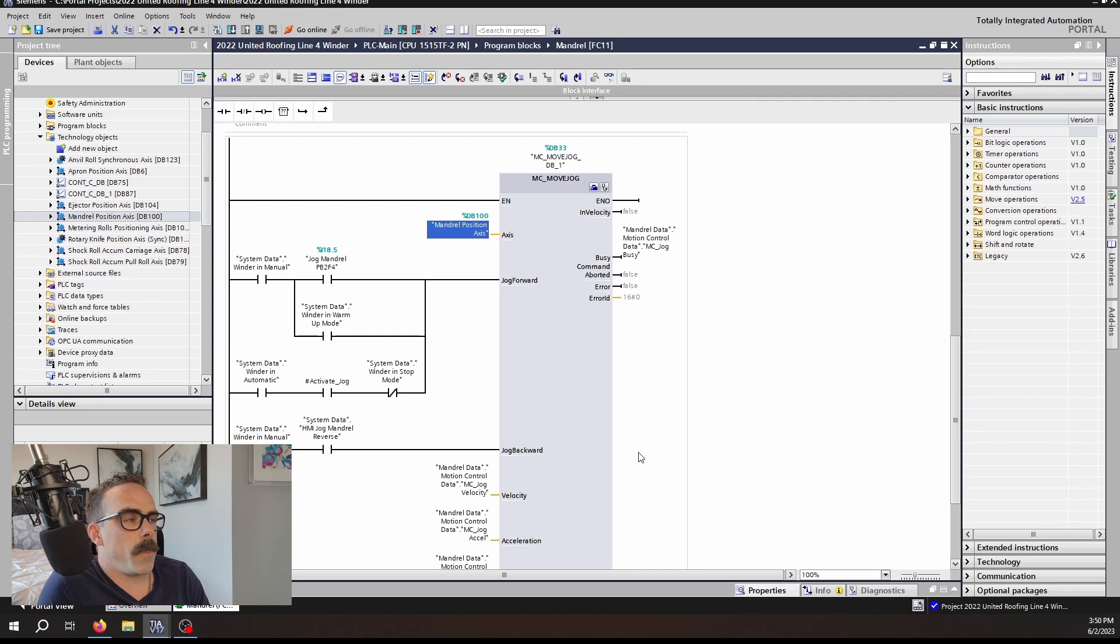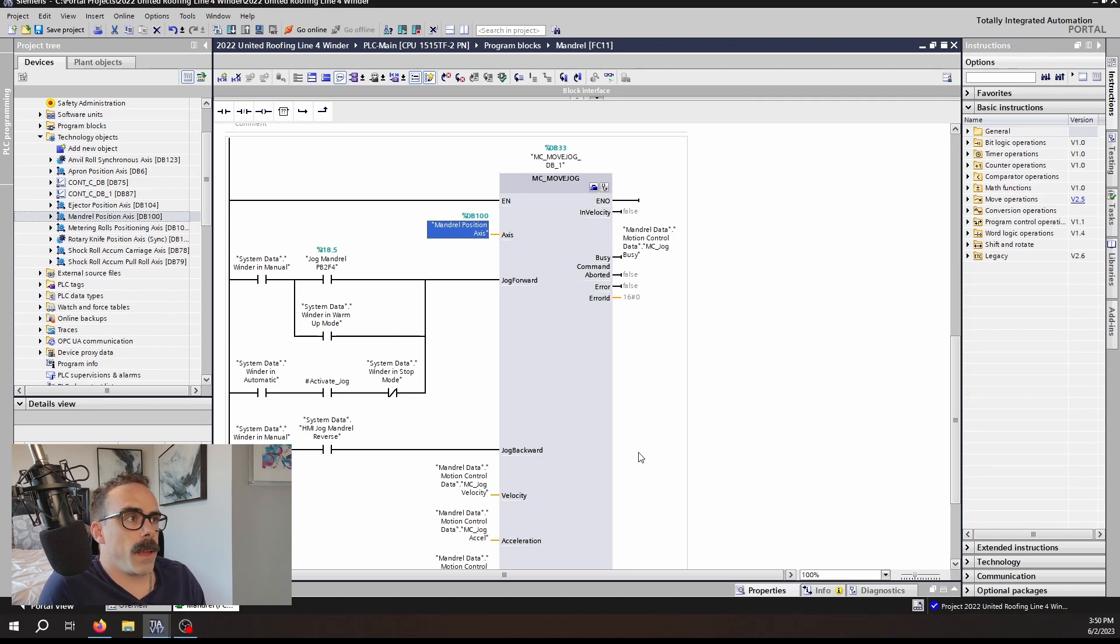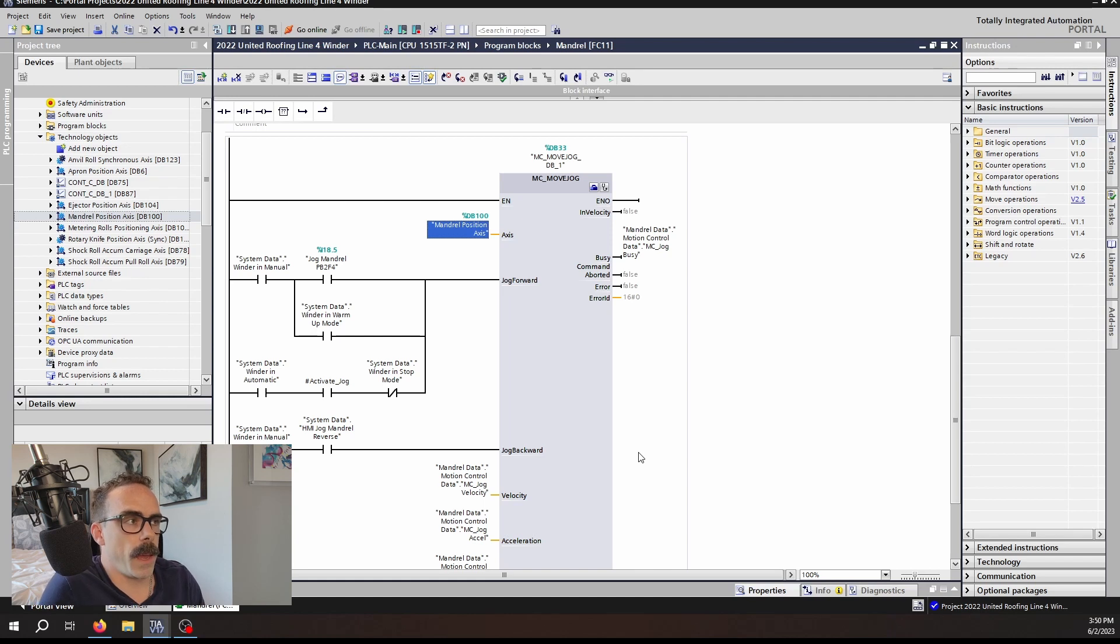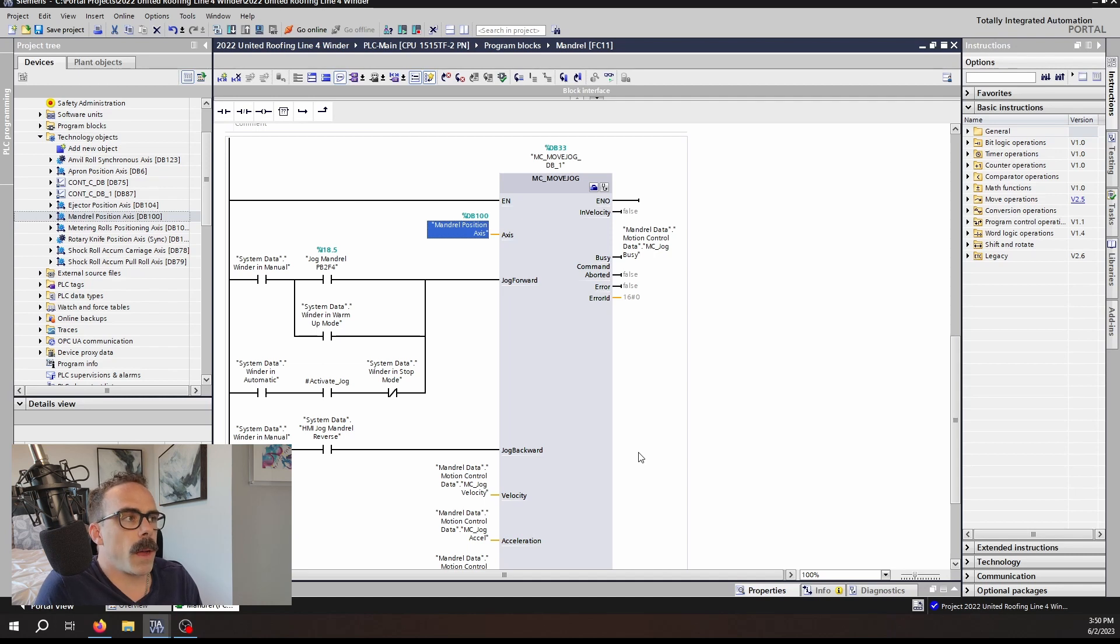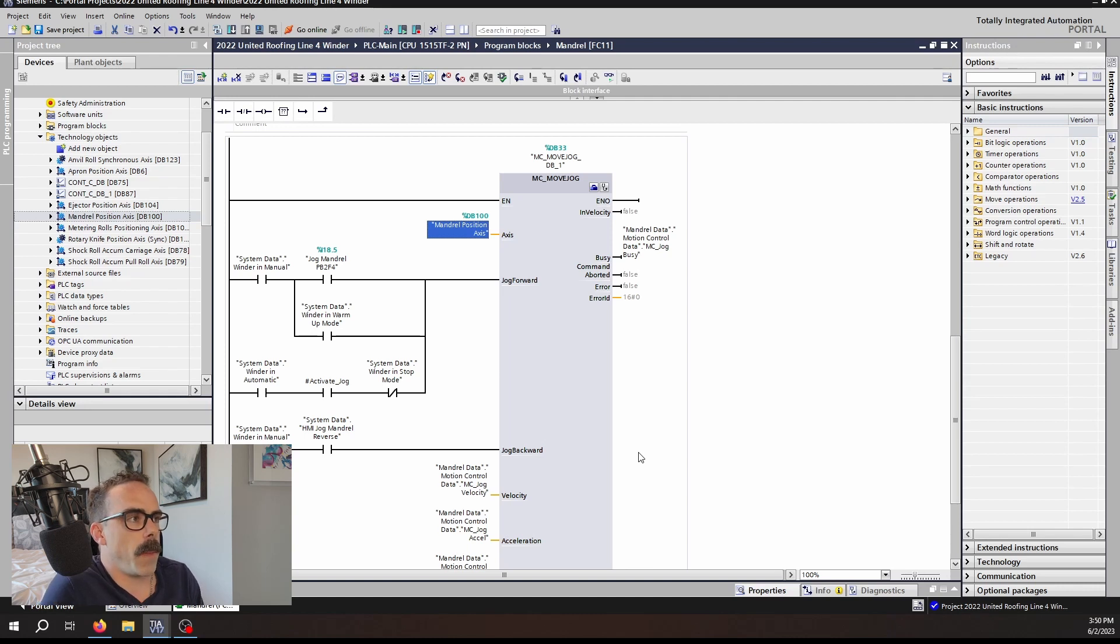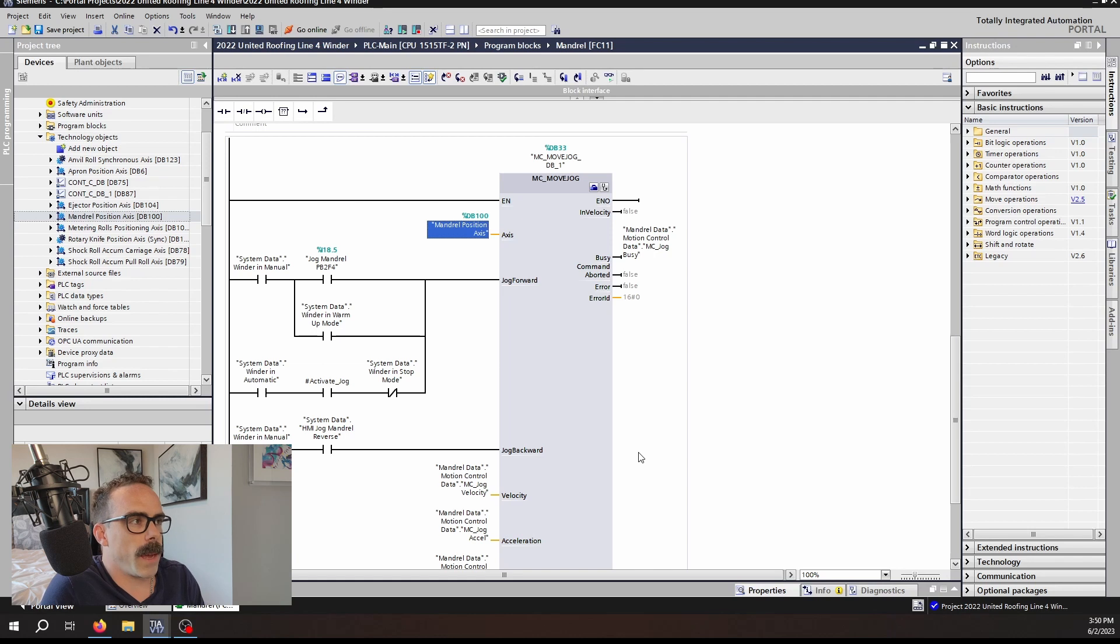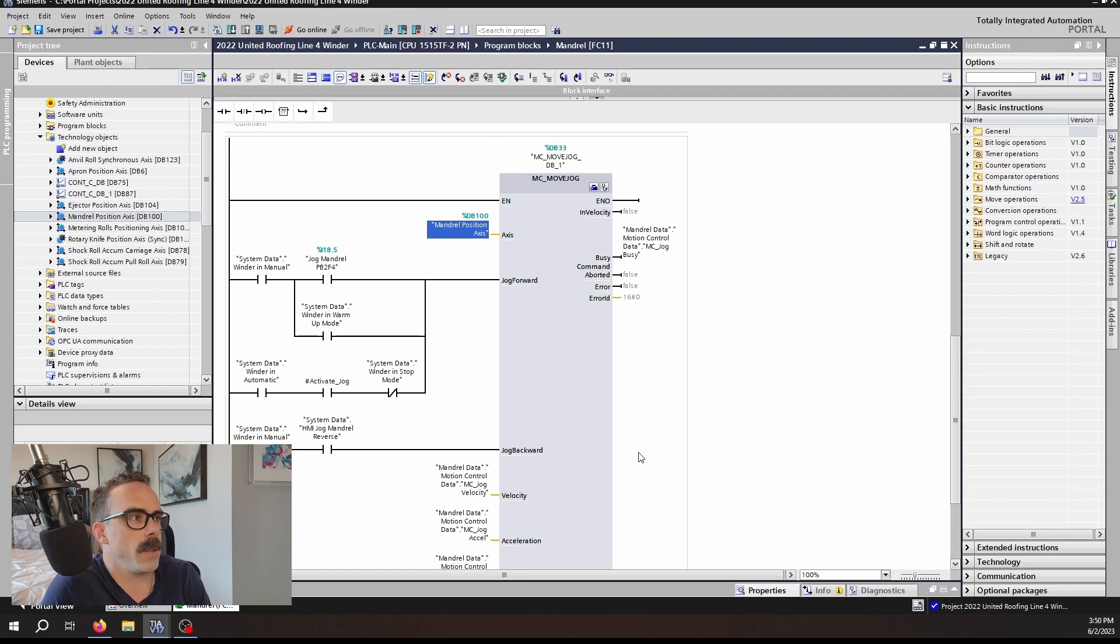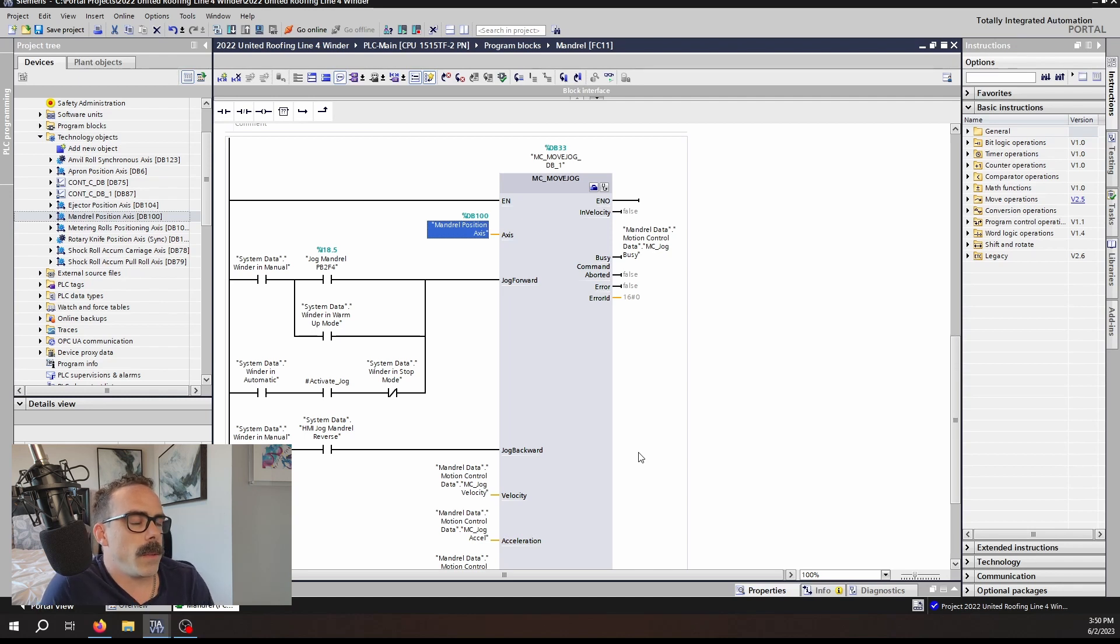As long as the function block is being executed with a Jog Forward or Jog Backwards command, the Busy bit will be true. As with all other MC blocks, if the command is overwritten by another command such as an MC Halt, the Command Aborted bit will go high. Again with all of the other MC functions, the Error and Error ID give significant diagnostic data.